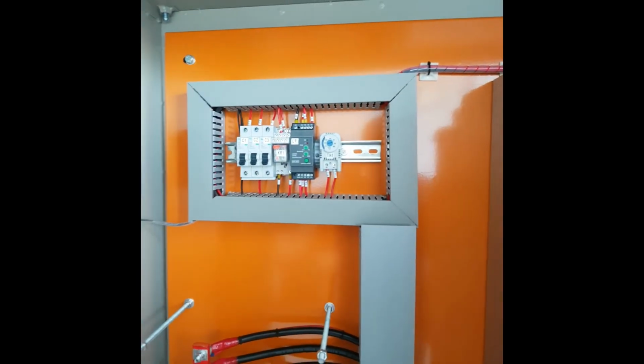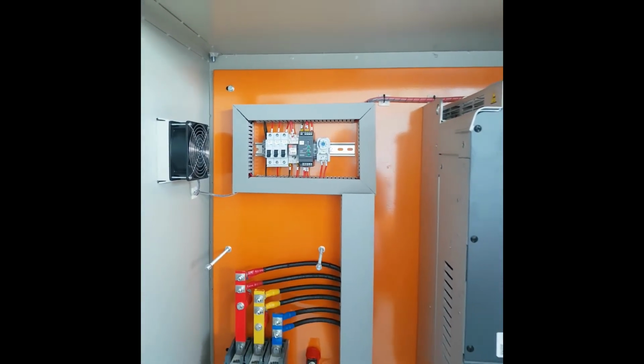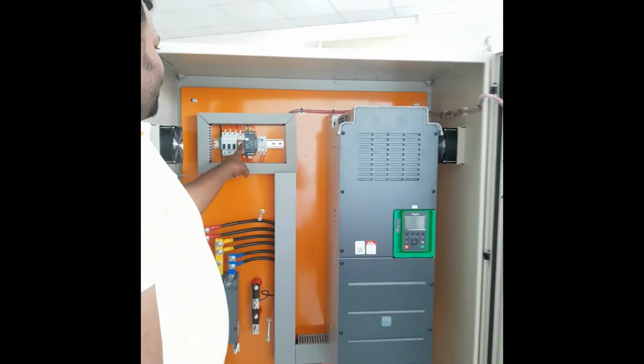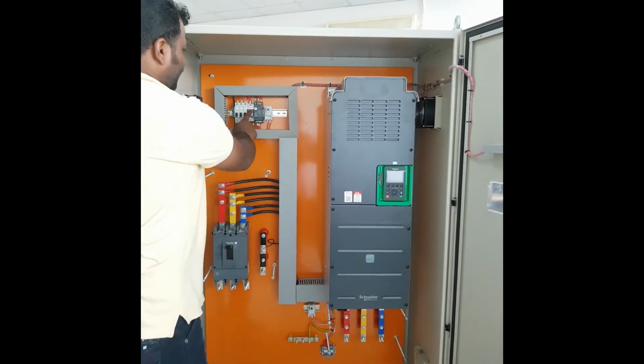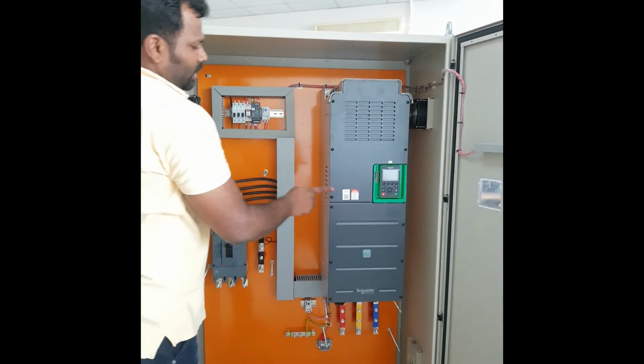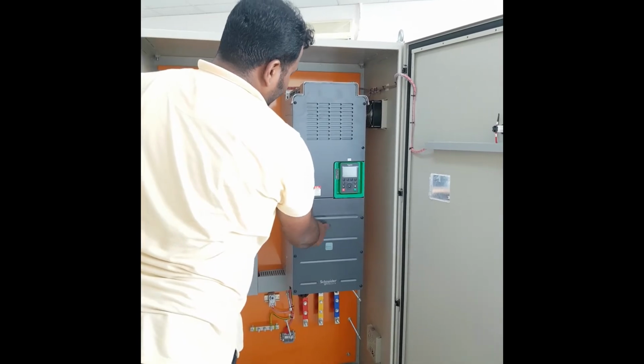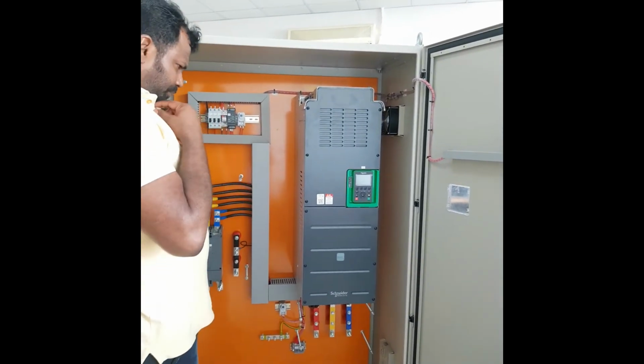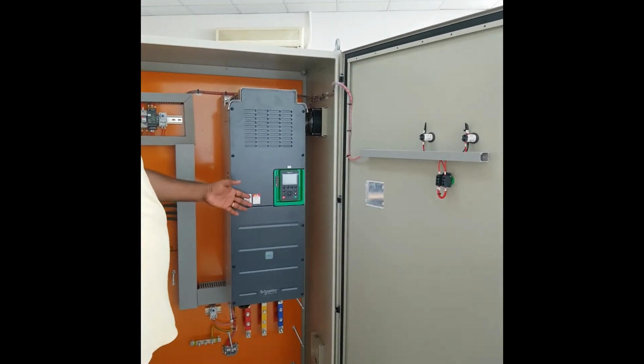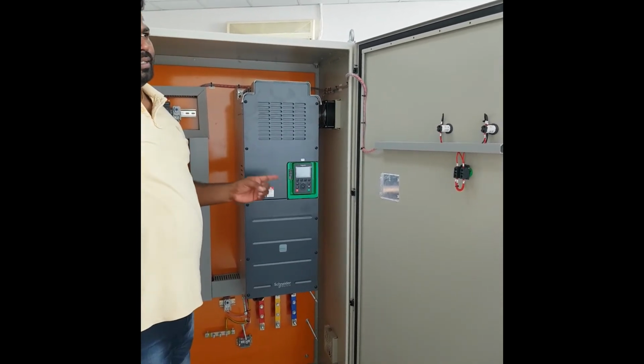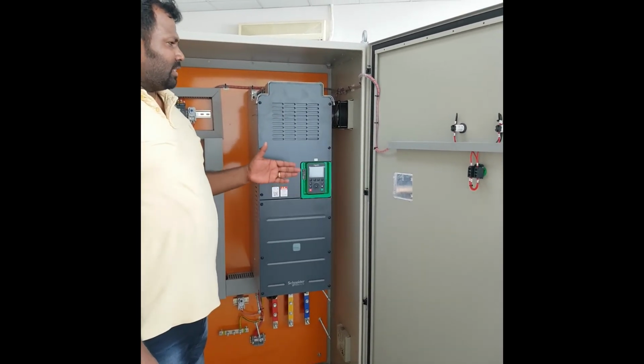Whenever you operate the selector switch, either from hand mode or auto mode, this relay will energize. Through this relay the start command will be given to the VFD. Inside there are control terminals. So the VFD will get the start command and it will start the pump as per the acceleration time.